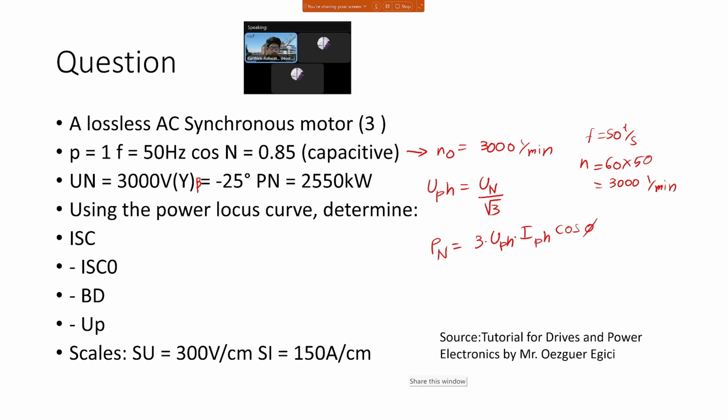In asynchronous motor, let's say you're using it to power a fan, right? If there is some kind of obstruction or friction, and the fan is creating more resistance, the motor will slow down while consuming the same power, more or less, or maybe a little bit more power, depends. But here it will not slow down. It will consume extra current such that it is able to meet this new torque requirement and will stay at 3000 rpm. So that helps us in a way. It's quite powerful because you have perfect control over the speed if that's what you want.